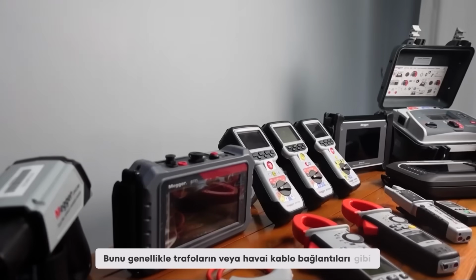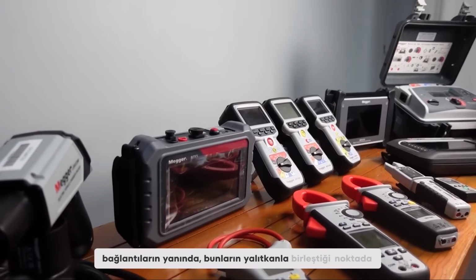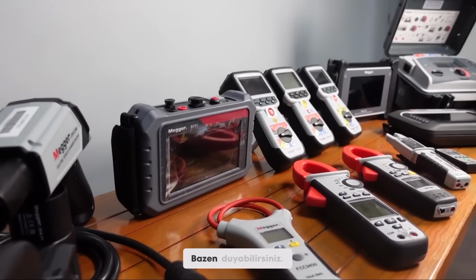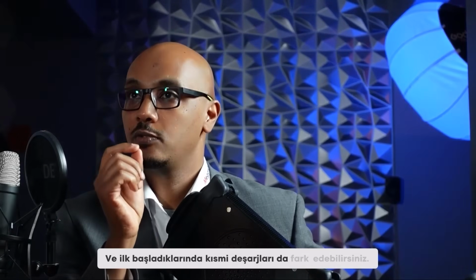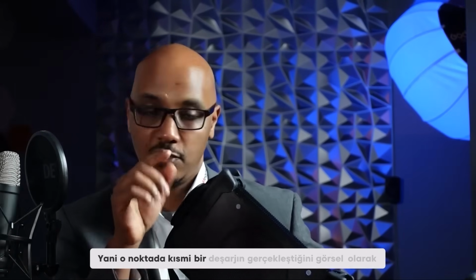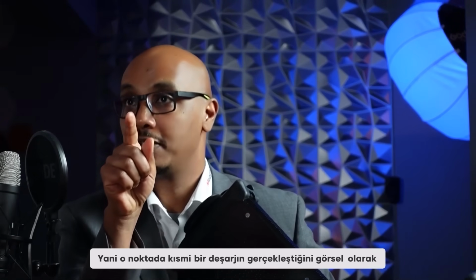When partial discharge happens in the audible range, you hear the buzz of electricity partially discharging. You often see that near transformers or overhead cable connections at the point where they connect to the insulator. This one picks up sound above 20 kilohertz, going up to 120 kilohertz, so you can detect partial discharges when they're first starting and visually see where it's happening. It's a very useful tool for walking around the site doing an inspection.